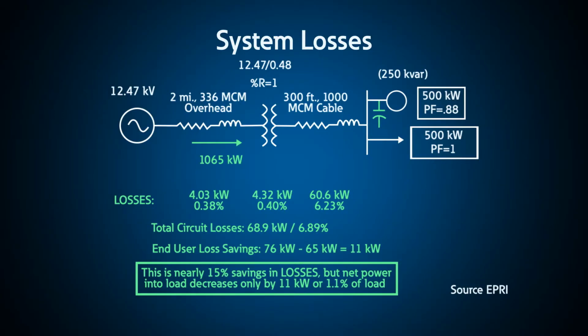So as EPRI said, you can only save what you have wasted. So therefore, you can only save up to about 4%. Typical losses on a power system are more like 1% or less. The ROI for a 1% savings is much more than 10 years if you were to install capacitors. This figure shows the actual system losses on a power system and the loss reduction by installing capacitors at the furthest point, at the load.